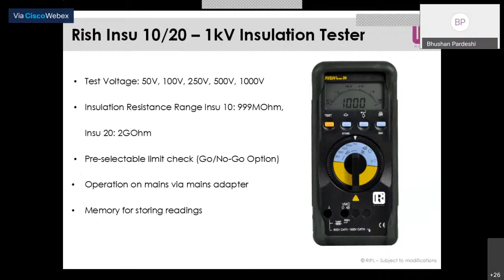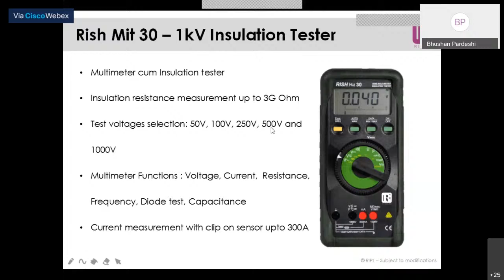Again, it has a pre-selectable test voltage from 50 to 1000 volt and multimeter functions like voltage, current, resistance, frequency, diode, capacitance, etc. Now in competition models like Motwane, you can consider, or Megger, they give current measurement up to 10 ampere or maximum 20 ampere. But in Rish Mit 30, we give 300 ampere measurement with the clip-on sensor. So this is one of the unique selling points of our Rish Mit 30. Basically, most of the competition gives up to 2 gigaohm, but we give up to 3 gigaohm with 300 ampere measurement.